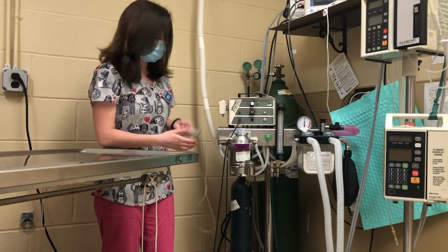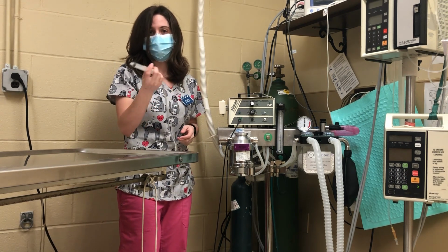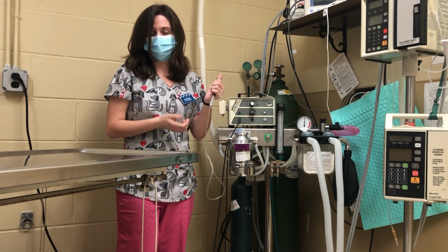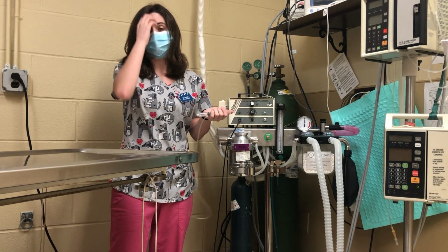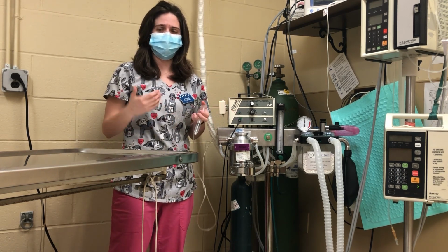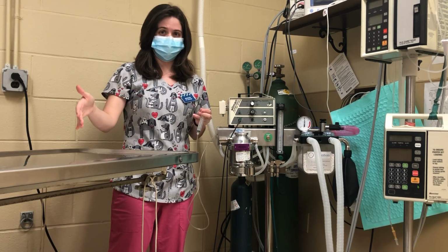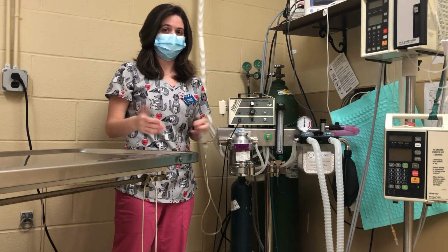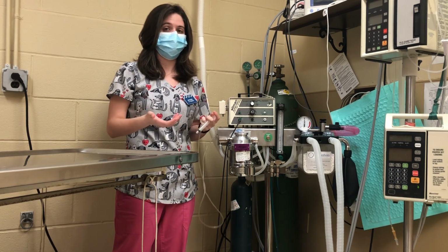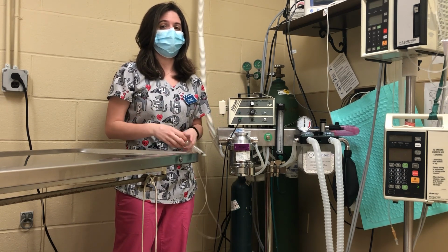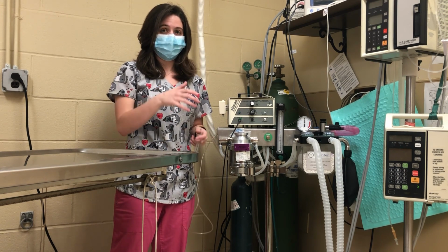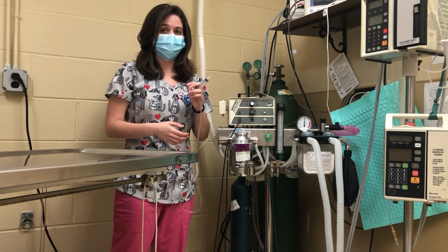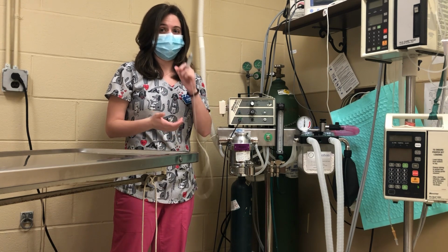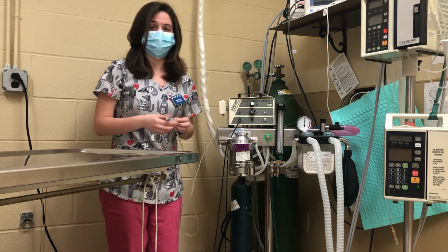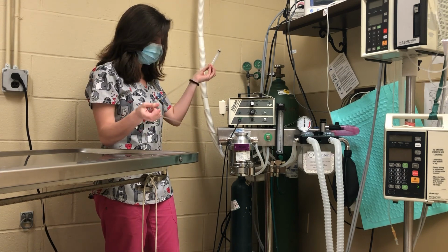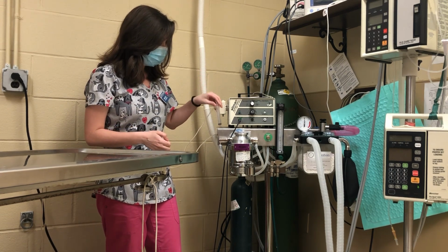And then we also have our cuff syringe. This is used to basically inflate or deflate the ET tube's cuff, either before surgery, when you're placing the ET tube, you want to make sure that there's no gas leaking and that the cuff is correctly inflated. And then at the end of surgery, when the patient is being extubated, you want to make sure that the cuff is deflated so that you don't cause damage to the trachea when you pull the ET tube out. We attach it to the machine so that we always have one handy.